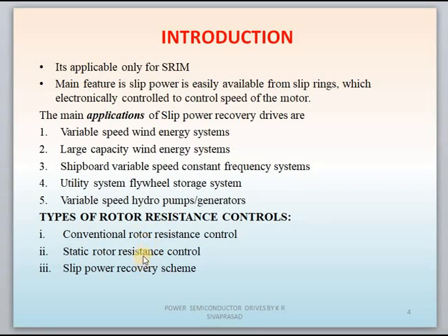In the above two cases, the slip power is wasted in terms of heat because we are using resistance to control the speed of the induction motor. That means we are wasting the power in terms of heat across the terminals. Whereas in the slip power recovery scheme, this slip power is returned back to the supply. From the supply again we are taking the slip power. Like this, we are recycling the slip power, so there is no wastage of energy here. That's why the slip power recovery scheme is a very effective method to control the speed of the induction motor.